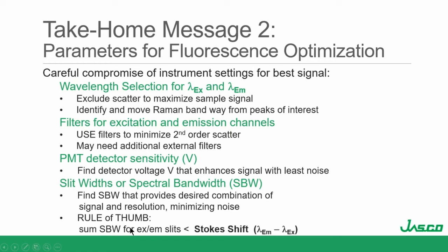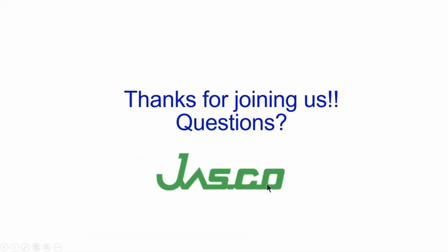One final rule of thumb: the sum of the spectral bandwidth for excitation and emission should be less than the Stokes shift of the molecule you're looking at — that'll help you minimize scattered excitation light in your emission as well. Thank you for joining us. We're happy to take any questions, and I hope you find this a valuable resource for your future fluorescence experiments.